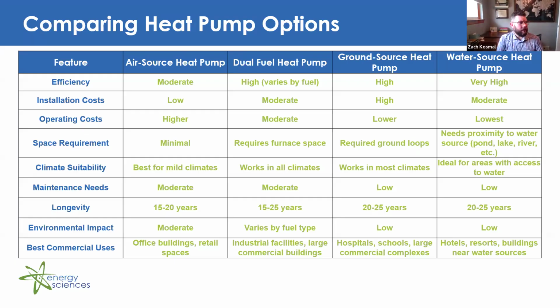Installation costs, you can see the trend here. You kind of move from lower to higher installation costs. Ground source heat pumps, they require drilling into the ground and installation of your ground source loop. That comes with a high installation price tag. And then in addition, water source heat pumps, they have more components typically, so that just comes with a higher price tag compared to an air source heat pump. Now, regarding operating costs, that kind of gets flipped around. So with your air source heat pump, you're dealing with that unstable outside air temperature, which may lead to going from partial load to full load. So that just puts more wear and tear on the equipment. And as you can see, for longevity, your air source heat pump is typically less than your dual fuel, ground source or water source heat pumps.